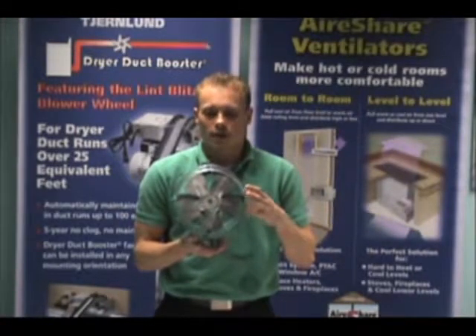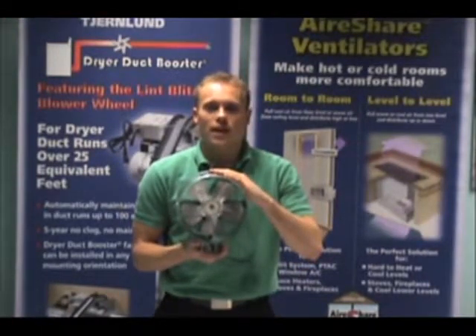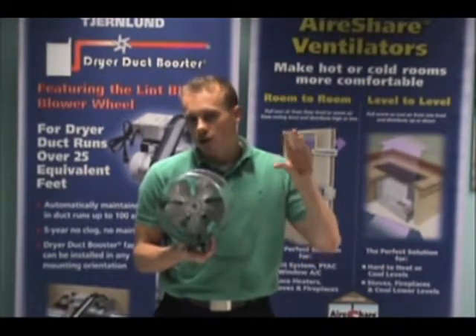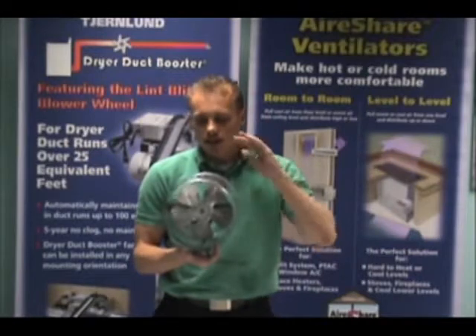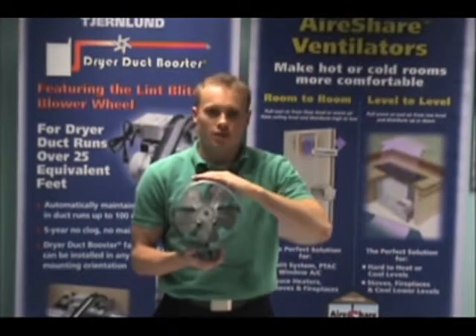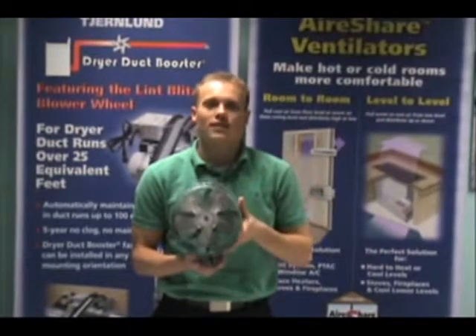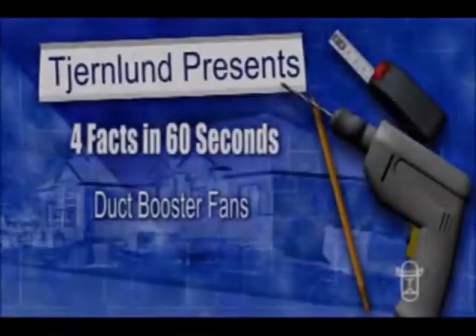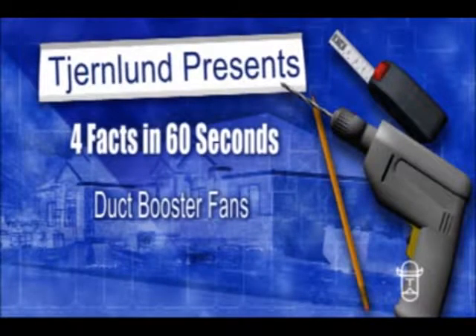And fourth, I get a lot of questions about location. Where you want to put this is right where your furnace blower is starting to die off, right when it's starting to get weak. This will pick up the speed of that air and boost it the rest of the way. That's 4 Facts in 60 Seconds on Tjernlund Duct Booster Duct Fans.